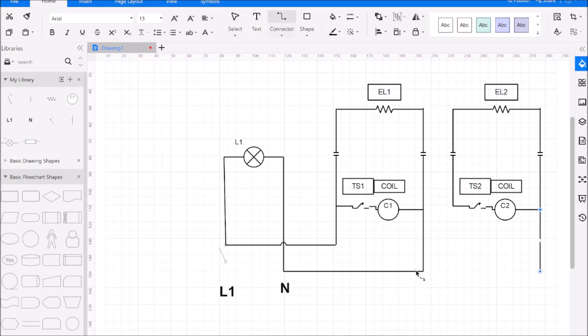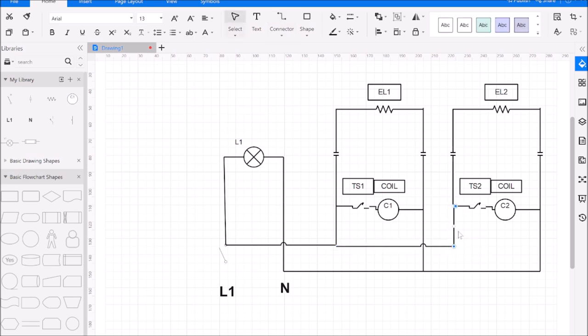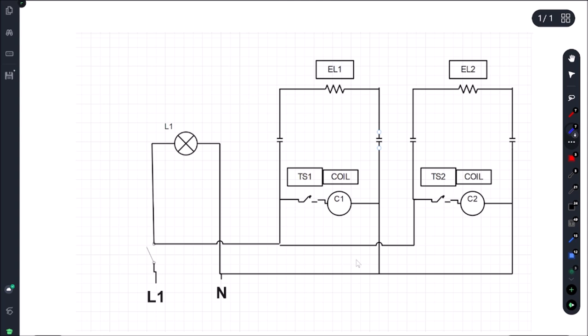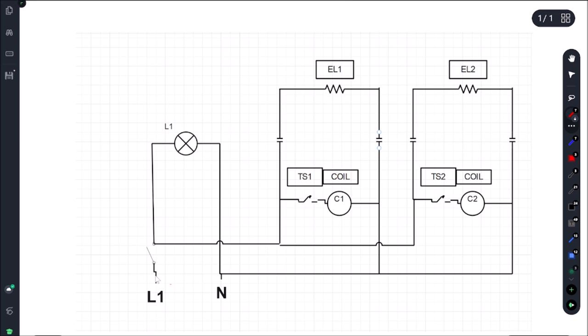This part is really important — knowing how to draw a schematic. If you can draw a schematic, the troubleshooting becomes so much easier. We have a complete circuit here. The way I explain everything is to think of everything as either a switch or a load. The load is obviously going to be the light and the two elements. The switches are going to be the contactor contacts and the thermostat, and the contactor coil actually becomes a load — the contactor is actually both a load and a switch, but that's a whole other thing.